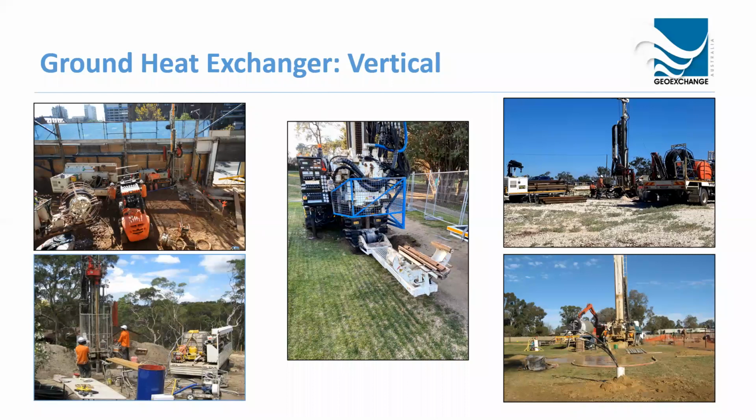If you ever see people out there saying, oh, we get X kilowatts per borehole on every borehole, or some sort of rule of thumb design, essentially it means they fundamentally don't understand how the technology works. Because obviously we need to work with the ground, we need to work with the environment there, with the soil type, with the temperature, with the soil moisture in order to get performance out of the system. You can't brute force nature as such, which is often what they'll try to do, or they'll be massively oversized or undersized. So, you need to get those systems done properly. And you need to get the design done properly, that understanding of the ground done properly.